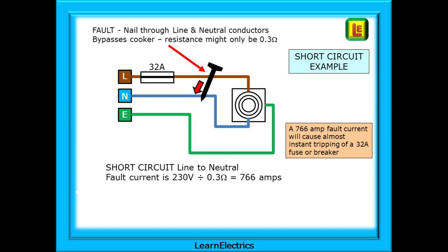Let's have a short circuit on this cooker now. Someone has put a nail into the wall and straight through the line and neutral conductors. The electricity, the current, will now flow through the fuse to the nail, along the nail, and back along the neutral. The current will effectively bypass the resistance of the cooker. All we are left with now is the resistance of part of the wiring, which in this example, we have said is just 0.3 ohms. If the current is bypassing the cooker, how much current is flowing? 230 volts divided by 0.3 ohms is a massive 766 amps. That little 32-amp breaker is going to trip almost instantly and make the circuit safe.